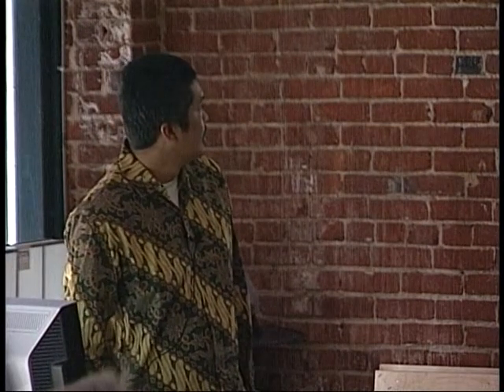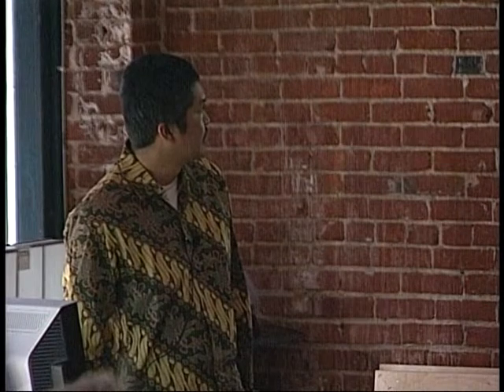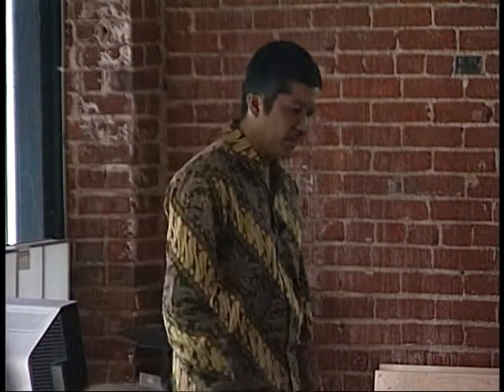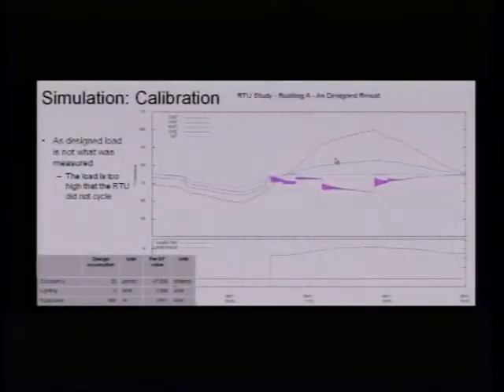So, I'll just go through this because how to develop this curve from the manufacturer's data will be another topic for our BSAC, probably the Building Simulation Users Group. So this is the result of the calibration. The idea is to have the unit as it is, then take all the design assumptions and run it. As you see, when we run the unit with design assumptions, the air conditioning runs very smoothly. Switch on once and never switch off, all day long.